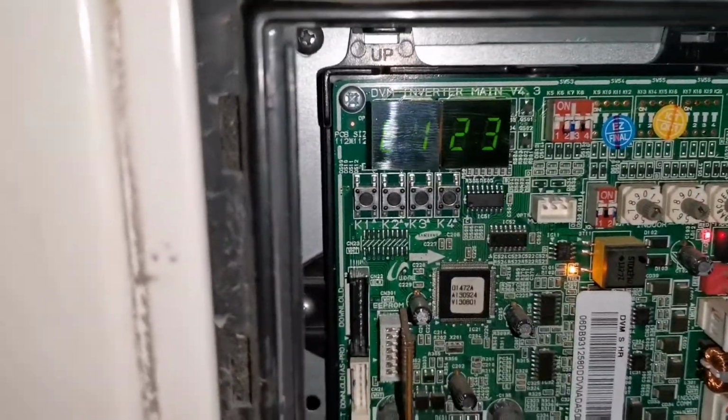or whatever problem you might have on that Indoor. So let's just close this panel. So right now we're at the master condenser, and that was on the main PC board. Its display segments show us which Indoor unit actually has that error code.